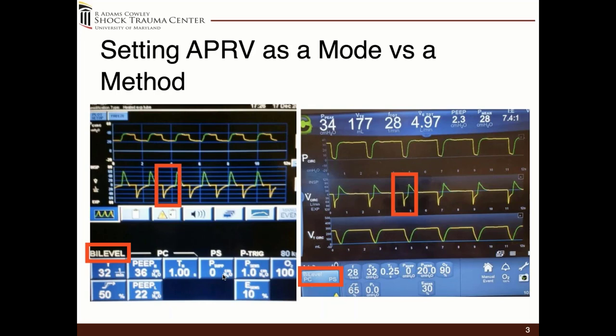First, I want to look at setting APRV as a mode versus a method. Both of these ventilators are set in the bi-level or APRV mode, but the waveform graphic looks significantly different between the two. Although the ventilator has the mode, there are various ways you can set it. On the left, we have a P high of 36, a P low of 22, a T high of one second with a rate of 32. On the right, we have a P high of 32 but a P low of zero, and we're using time to control our end-expiratory lung volume — in other words, setting the PEEP.